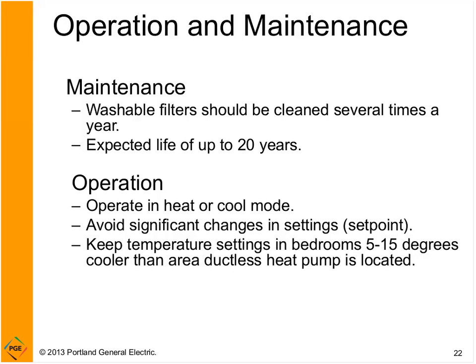And keep temperature settings in the bedrooms 5 to 15 degrees cooler than in the area where the ductless heat pump is located. We want the ductless heat pump to be the primary heat source, so that warm air is going to the cooler areas where the baseboards are located, and the baseboards aren't operating or are operating very little.